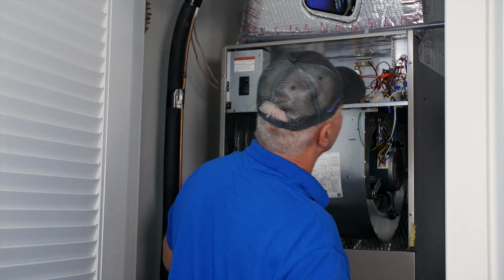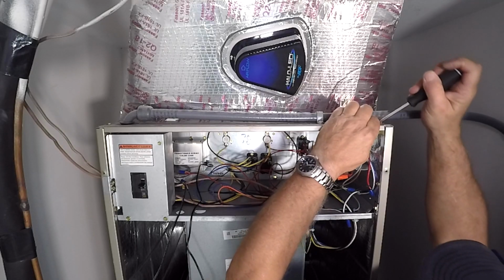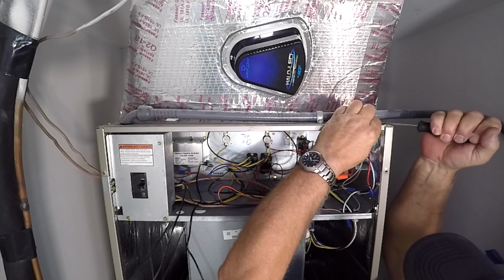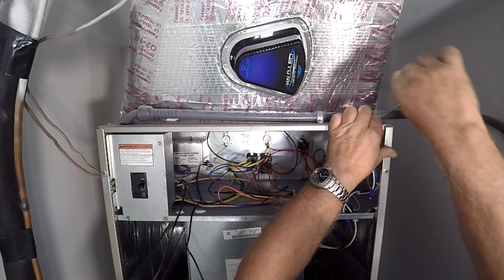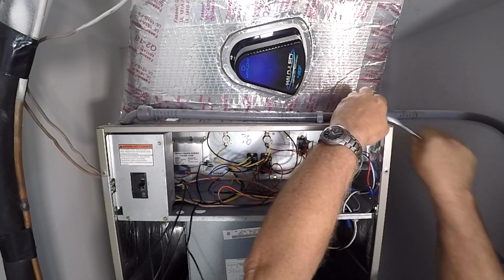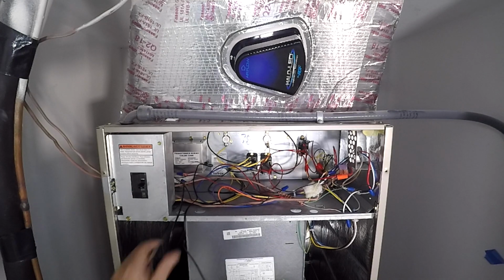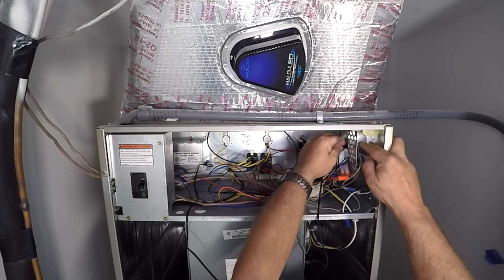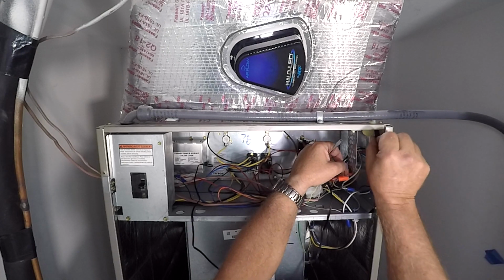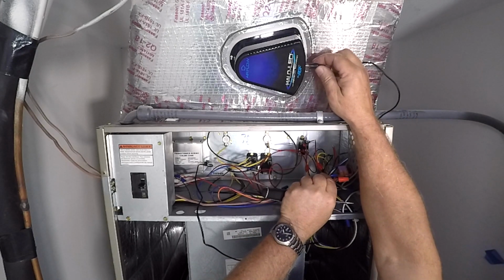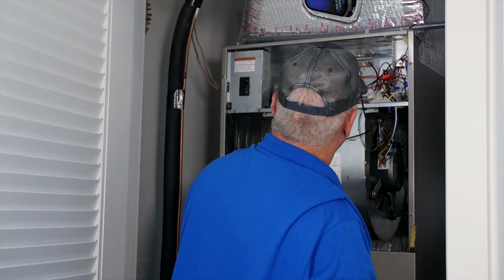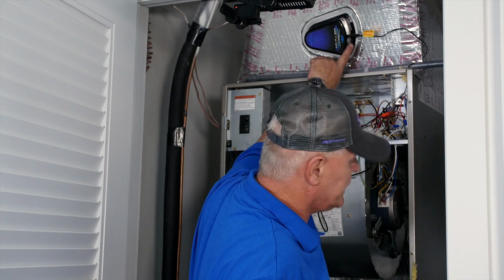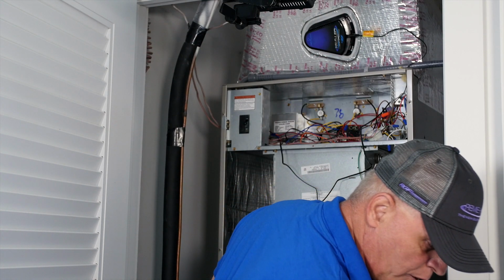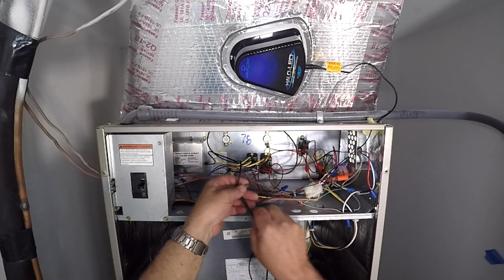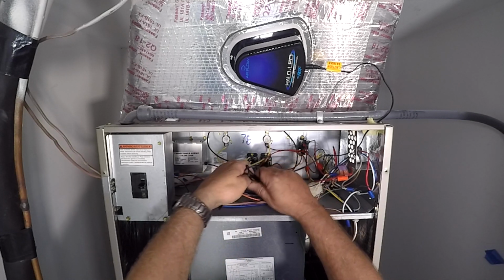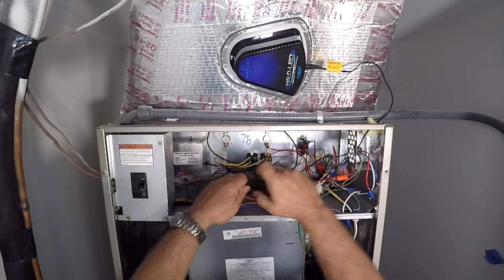Now all we need to do is run our wiring out through the unit. This is an alternative thermostat wiring plug in the unit that I am taking out at this moment so I can get my end of my cord through it. The end of the cord has a kind of a large plug on it, so sometimes it's a little difficult feeding it through. And then once you have it out, it will plug right directly into the back of the LED unit, and when this unit cycles on, you will see a light right here. That tells you this unit is turning on and off. Try to neaten up your wiring a little bit. We now have our wiring completed on it. We have our unit installed. And all we have to do is put it back together.